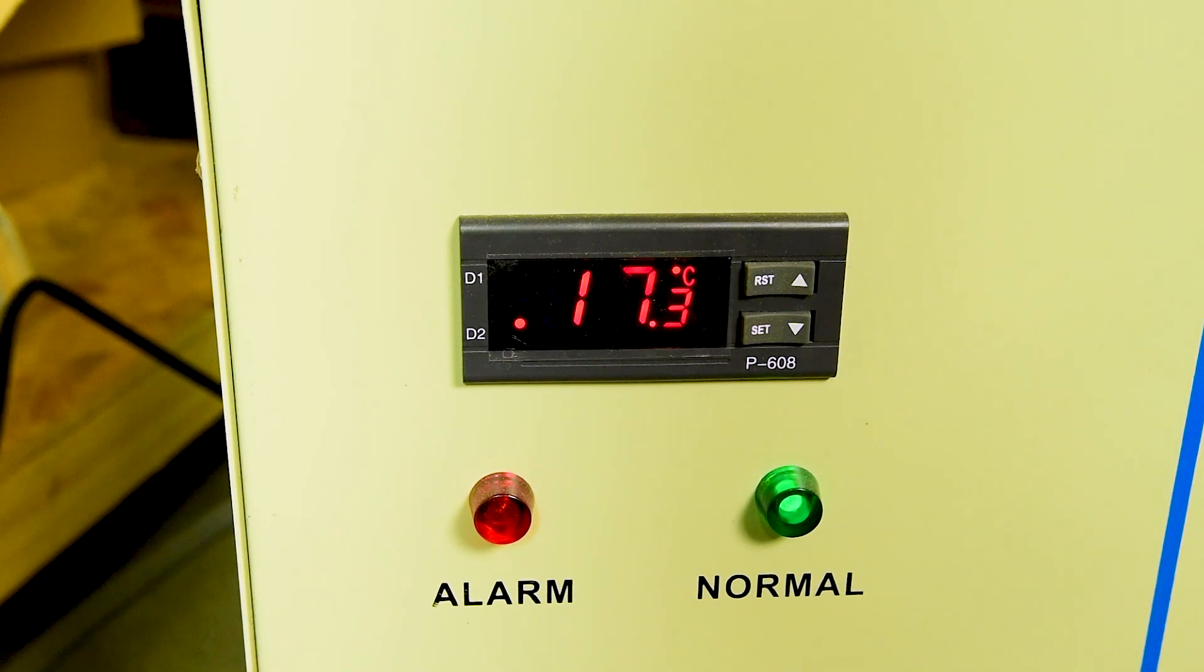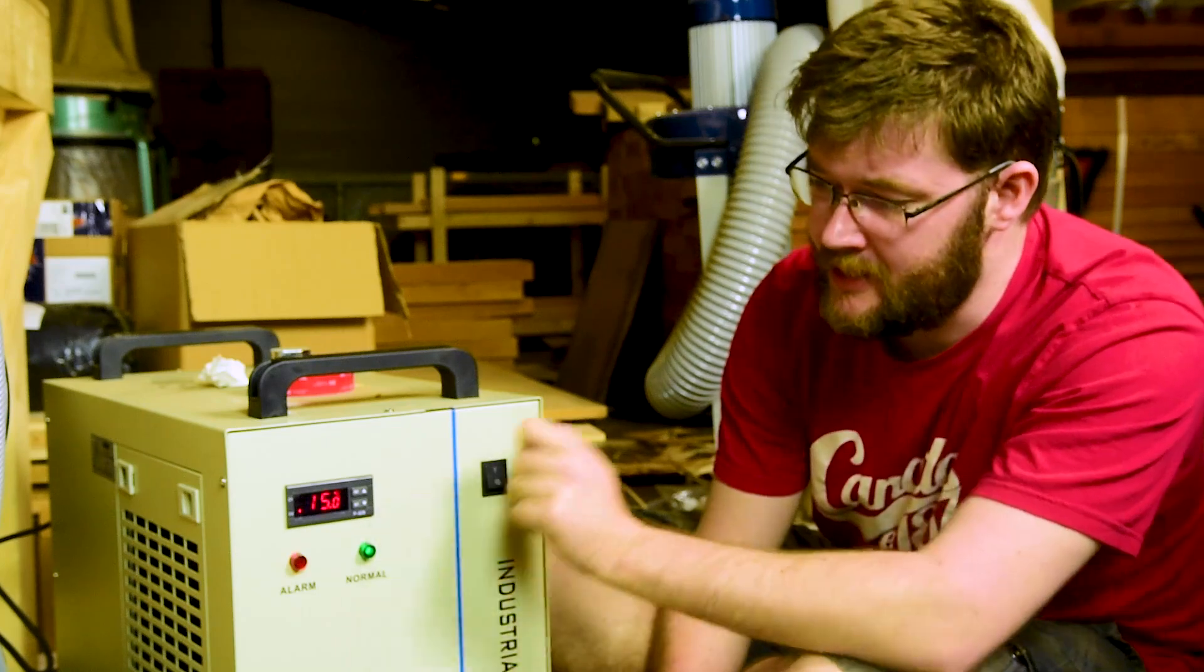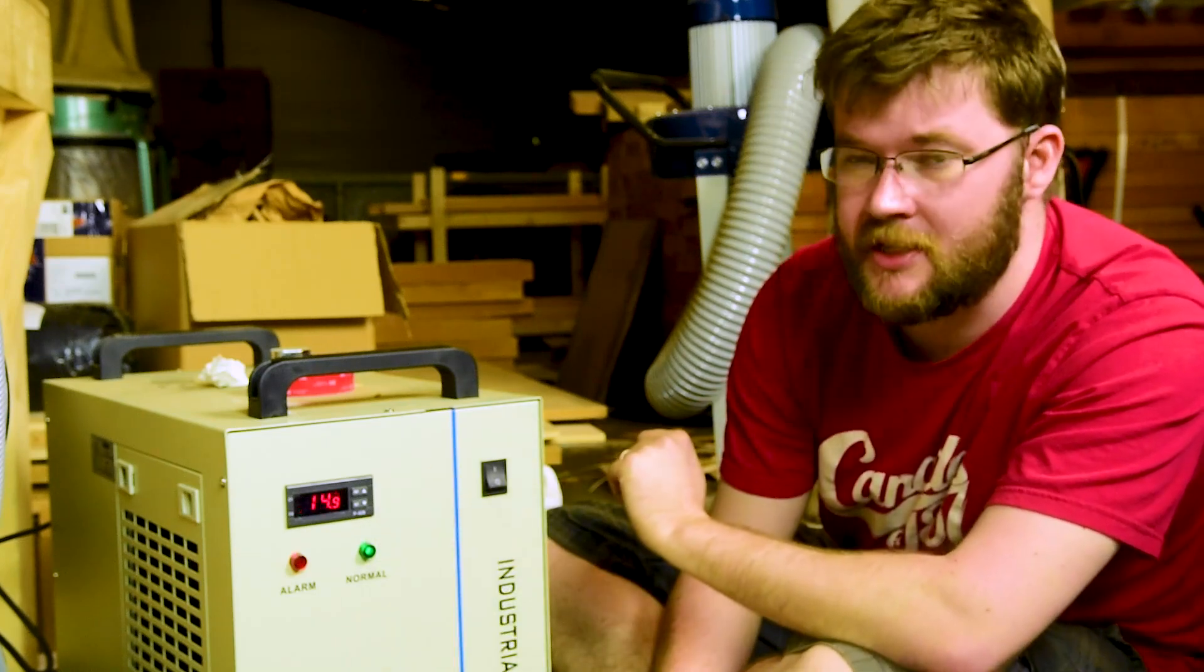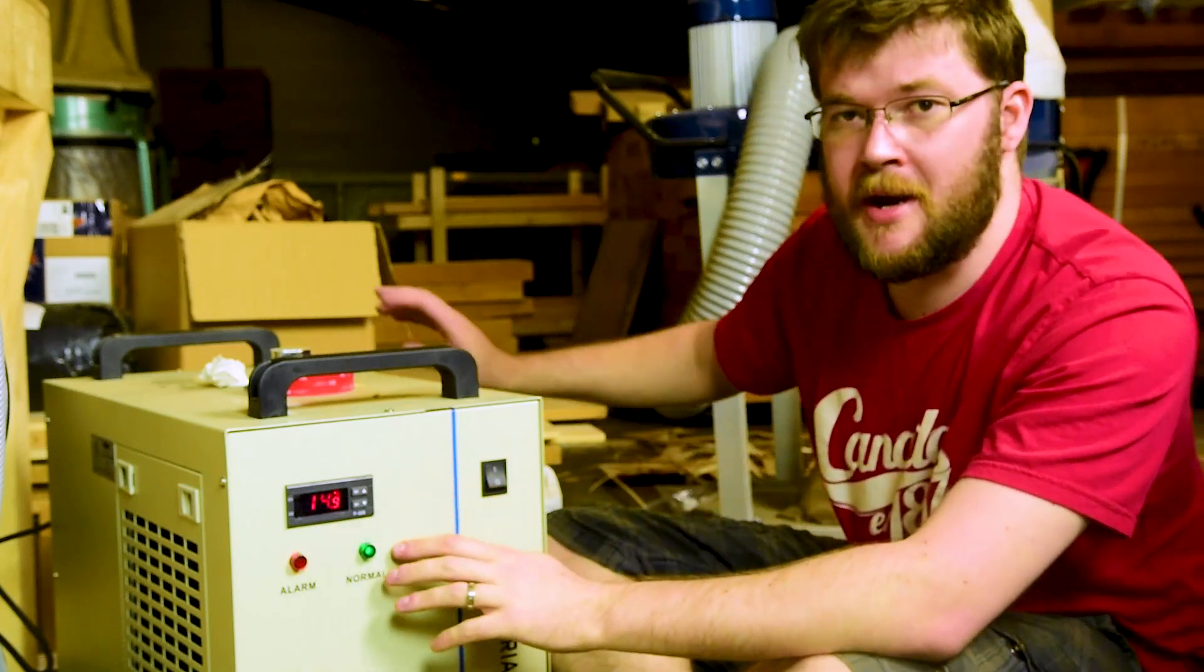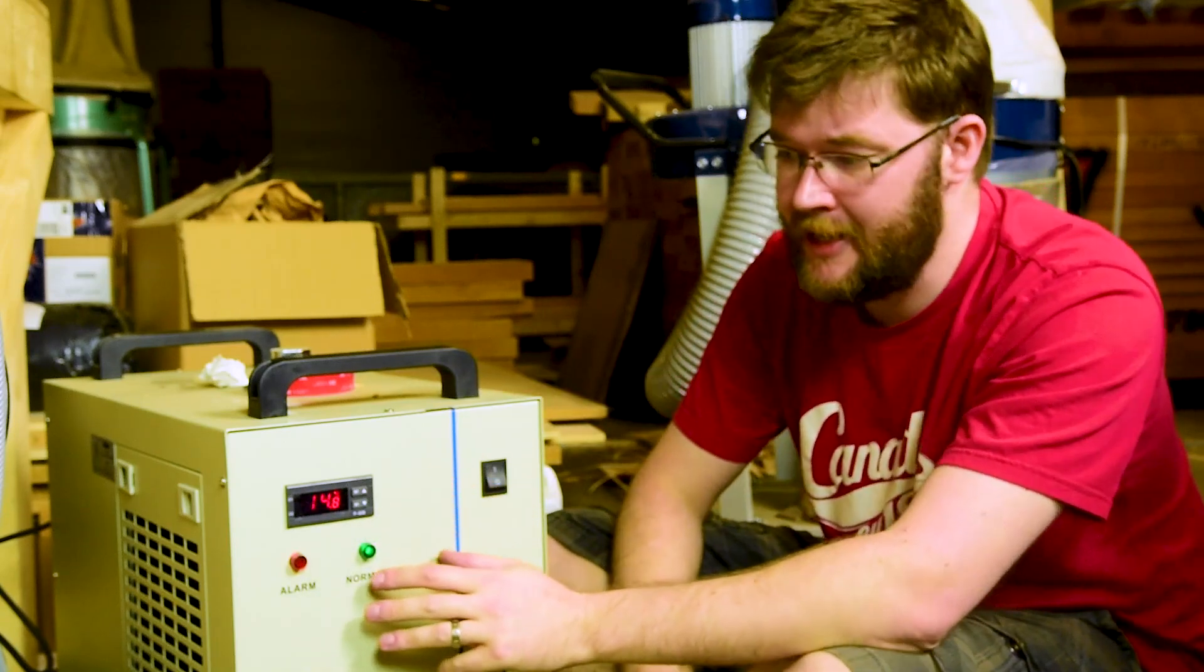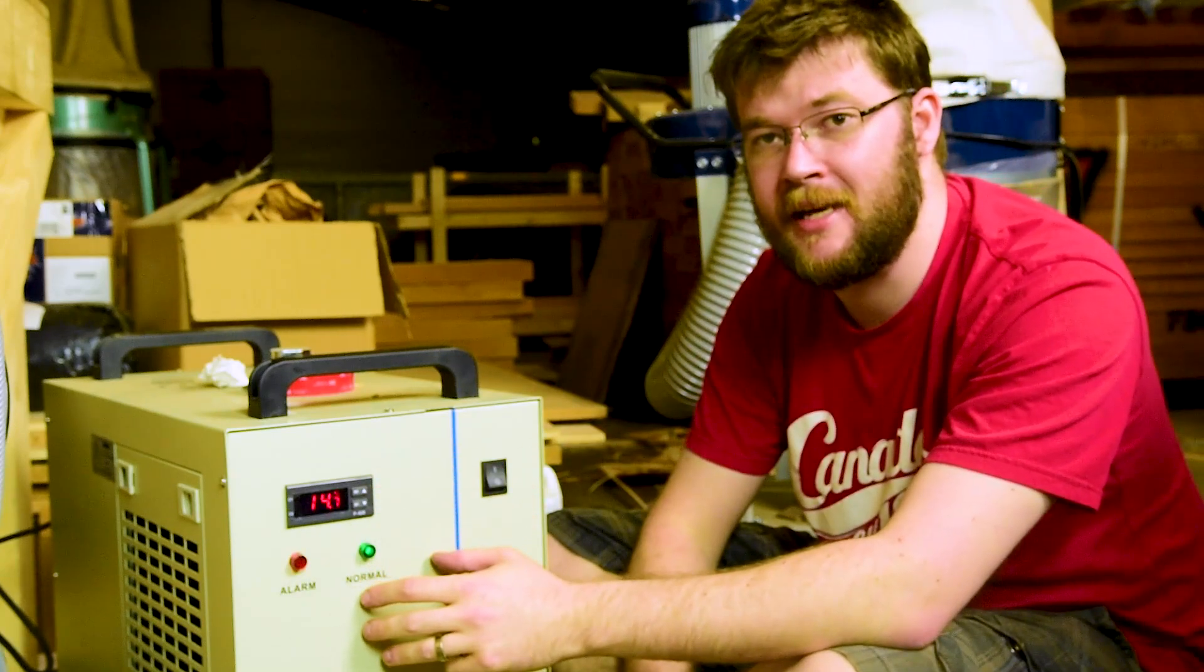Now this is going to kick on and start chilling the water down. There we go. We're at 15 degrees as we set it. Should switch off in just a second. There we go. Chiller is off. Now just running the fans to cool down the radiator. It's going to drop a little bit more as there is quite a bit of thermal mass there.